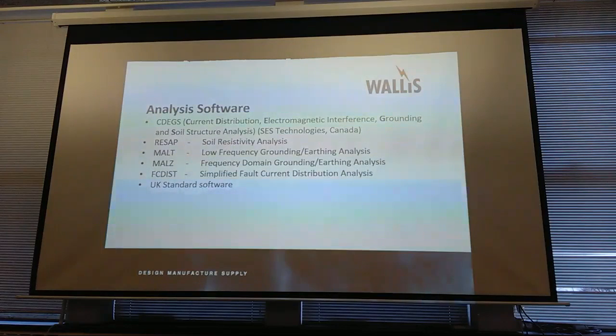Then there's the FCDIST, which is a simplified fault current distribution analysis. What you can do on that is put in your distribution substation, your feeder cable parameters, your sheath impedances, mutual impedances, things like that, and it will give you an idea of the percentage split between the general mass of earth and the cable sheath. There are also some very good formulae in ENA TS 41-24 and S30, both very good documents. To do that longhand, with MathCAD or something like that, is fairly straightforward actually.